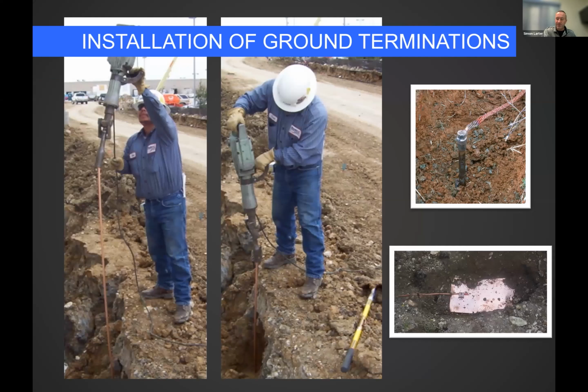Of course, you've all seen this stuff before. Again, exothermic welding is fine for us. We tend only to use exothermic welding in the ground. We do not use exothermic welds at roof level because roofers don't want sparks all over their stuff. That's not too good. So we will always use bolted connections at roof level. Every now and then we see a spec where an engineer wants everything welded, and some older lightning protection systems will have welds at roof level, but we don't recommend it and we don't use it anymore. So you will rarely run across that unless it's a very old building that somebody's re-roofing.